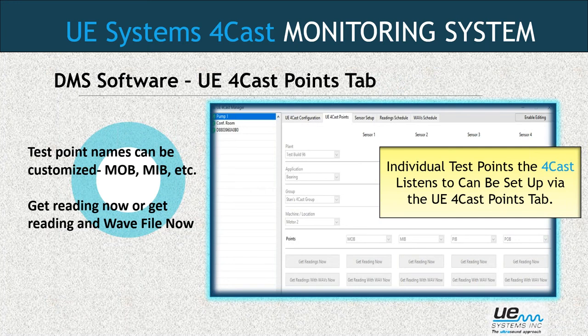This is also where we can get a reading now. In other words, once the sensor's activated, we can get a reading immediately and get a reading and a wave file immediately. Really valuable if you've had a bearing or a motor replaced. Very valuable for new installations where you want to hook a 4Cast up, and before you even get started on data acquisition, you want to go in and get a reading right now.